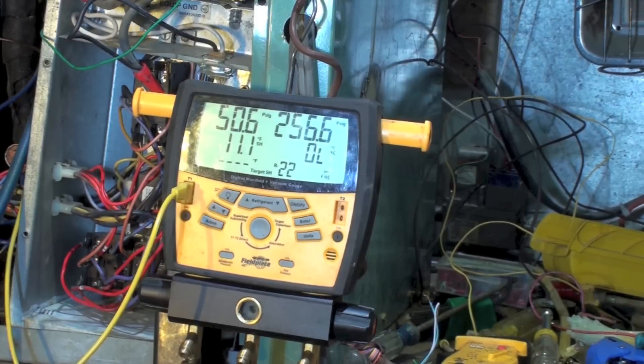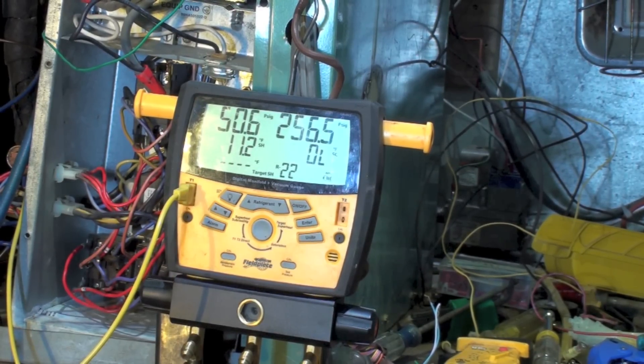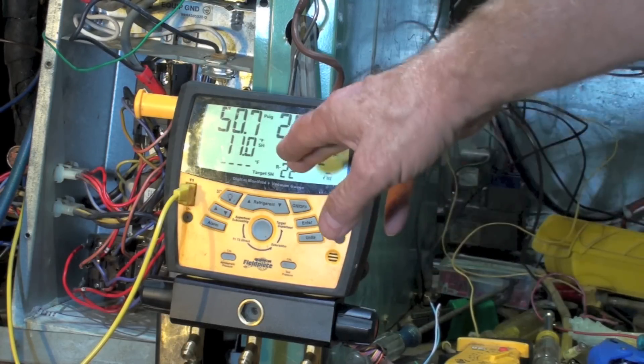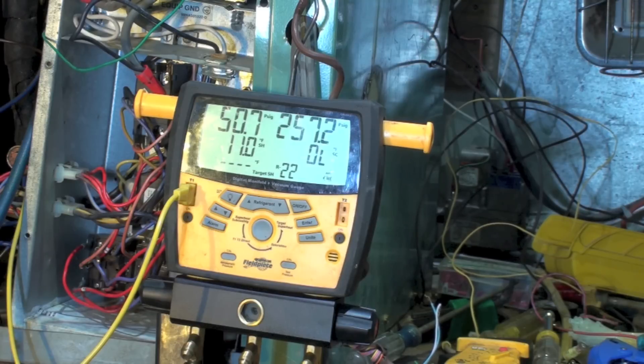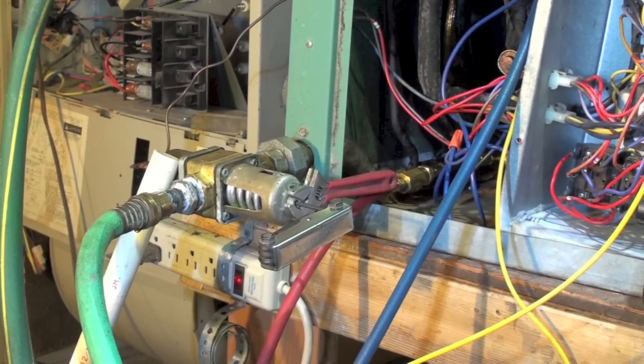Okay, here's a look at our suction head on this with that 40-degree temperature water. I'm below freezing here, which bothers me a bit. The head is probably fairly close to what you'd expect. I got an ambient coming in of about 70 degrees. The superheat is about right, but I'm going to see if I can raise this up a little bit. I can raise this with the water valve because I'm going to adjust that water valve.